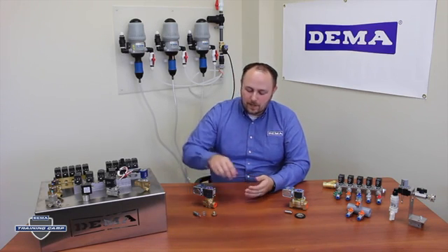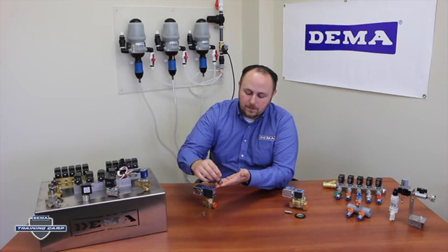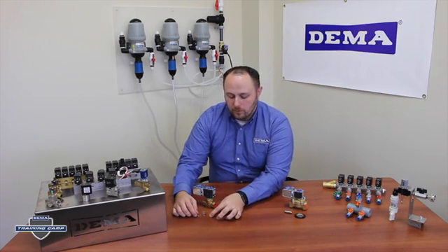The A series and the high pressure valves are our pilot piston valves. There is a piston on the inside that travels up and down freely and a plunger that acts on that piston. When the plunger is on the piston it commands the valve to close, and when the plunger comes off the piston it actually opens up, letting the water flow through the valve.